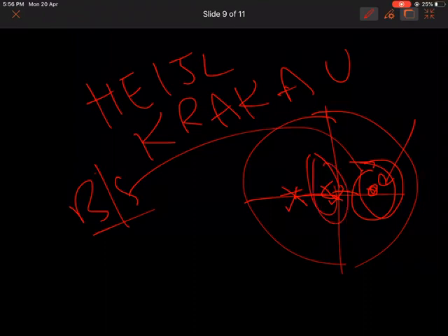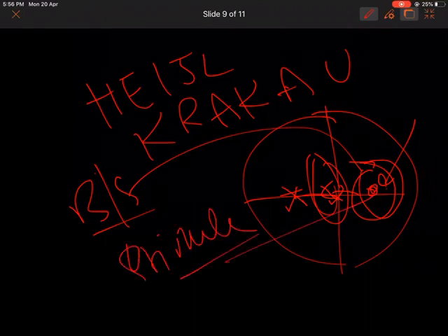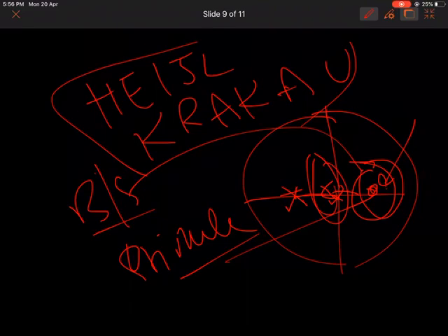Now the patient's blind spot is here. Now it has shifted. The patient has moved his eye. So any stimulus on the initial blind spot, the patient will detect it and he will trigger it. The previously undetected area of the blind spot, now the patient starts detecting stimulus in that. So this is the Heijl-Krakau method of detecting the fixation loss. If it is more than 20%, the test is said to be unreliable.